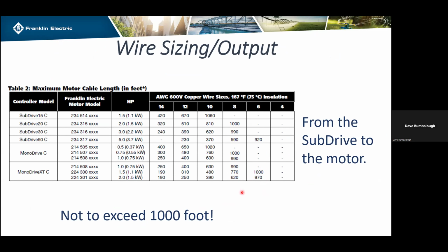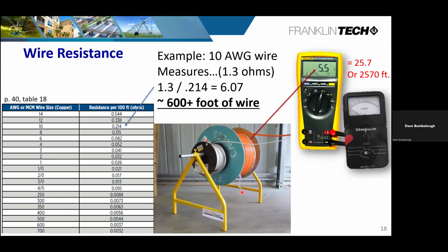Anything more than that, you'll have to add additional equipment, and that's usually in the form of a sine wave filter. Those will help suppress any kind of reflective wave or voltage spikes that may occur with a drive. The other function that you can use your ohm meter for is checking a spool of wire. Now, they do make a meter for that, but no sense buying additional equipment because you've already got a meter that's capable of measuring that.